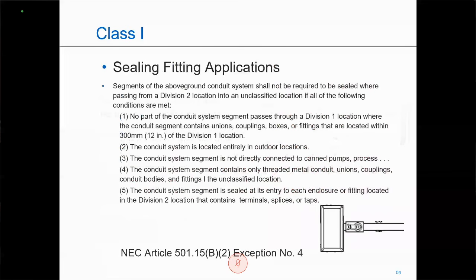And then we have exception number 4, which is a very common exception because this is an outdoor exception. A lot of our hazardous locations, when you think about refineries, chemical plants, and wastewater treatment plants, are in that scenario. If the area is a Class 1 Division 2 area, and the conduit does not pass through a Division 1 area with any couplings or unions or fittings, it's entirely outdoors, it's not connected to that process application, it's above ground, and it's all metal conduit, I only have to seal at the very first unit. I don't have to seal again after that.